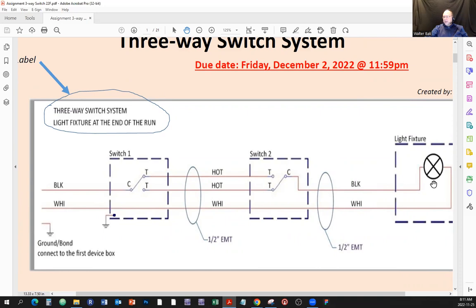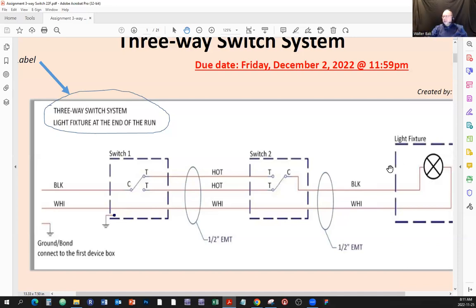Sometimes somebody gets the idea that if it's supposed to be at the beginning of the run, they just flip the whole image with the power supply on the right — no. It's still at the end of the run. If it's supposed to be at the beginning of the run, just take the light fixture and put it here instead of the switch, and the switch goes here, with power supplied to the light fixture. Please remember that.